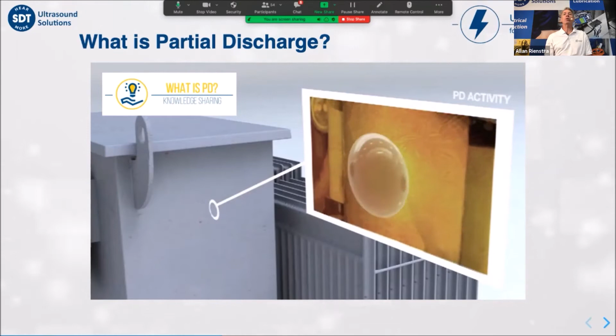Partial discharge is an atomic reaction which, due to the movement of electrons, ionizes the air molecules at locations of high stress. This ionization splits the oxygen molecule and allows it to form ozone and nitrous oxide, which in their normal states are generally harmless. But when you mix them with water vapor, they become corrosive. And if you've ever walked into a substation and noticed that smell of ozone, then you've witnessed firsthand the presence of partial discharge. Internal discharges exist beneath the surface of these components.